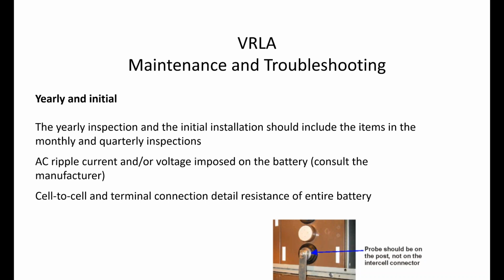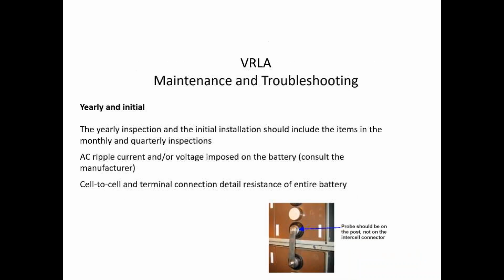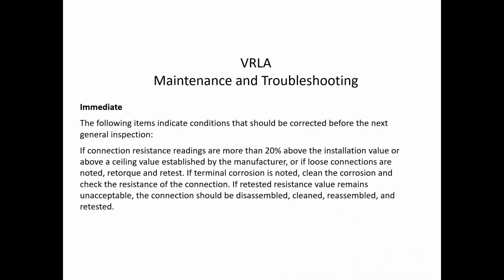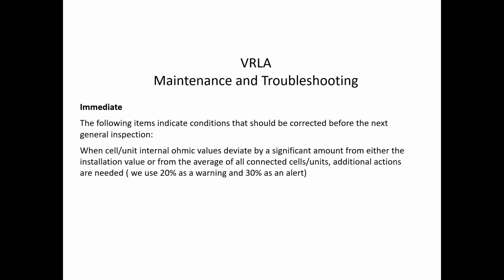And then let's see, a second, what did I do here? And again, these are IEEE. So the important thing is, okay, now I'm doing all these readings. What, according to IEEE, requires immediate attention? So again, to kind of prioritize what's a real red flag and what I need to worry about. Connection resistance, more than 20%. So they're saying, hey, if you see a change in those resistance readings, that's something that's going to require immediate attention.